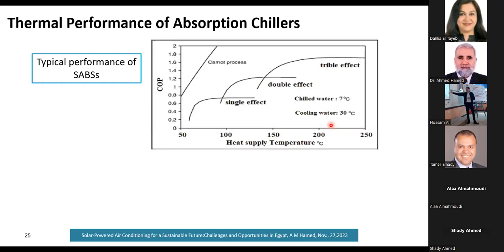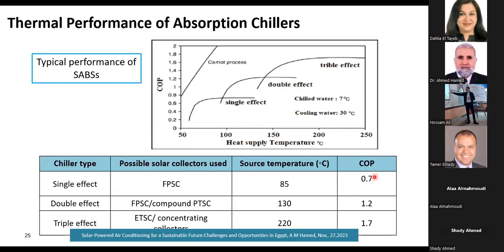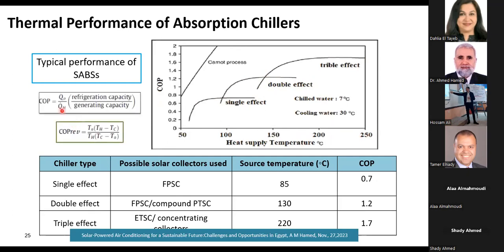The typical performance of the absorption chiller depends on the number of effects and the level of temperature used to power the system. As we can see, the single effect has a lower COP, the double effect has higher values, and the triple has the highest value of COP. In this case, the coefficient of performance is defined as the refrigeration capacity over the generating capacity. Of course, the two elements in this definition are heat, either heat of cooling or heat added for regeneration. And this is the definition of the reversible COP.